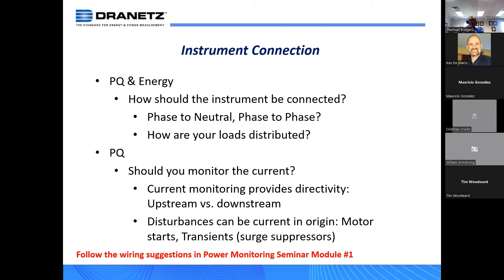Even if you don't monitor the current, you can still see where events might be occurring simply by monitoring the neutral or ground voltage. When you have a fault occurring at the load, the load is going to draw fault current that returns through the neutral. That current interfacing with the impedance of the neutral means that even though you might have a dip in the voltage due to the fault, you'll have a corresponding increase in voltage on the neutral. That's an example of monitoring PQ events without having to monitor the current.